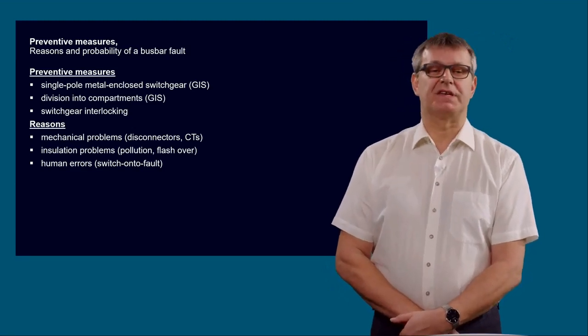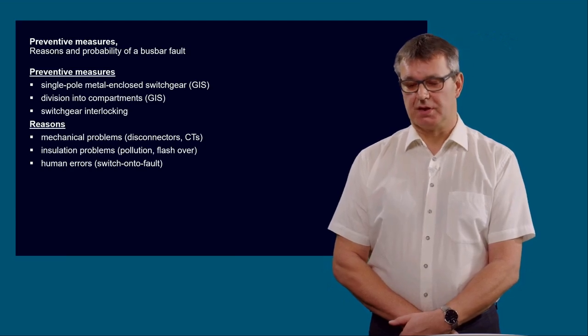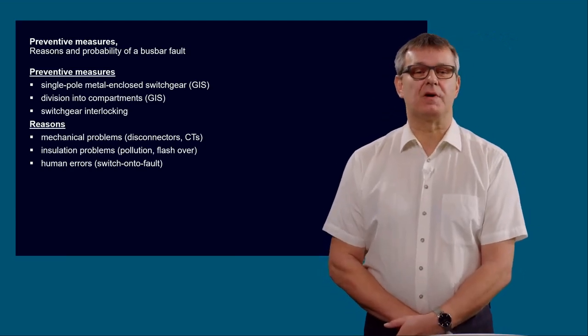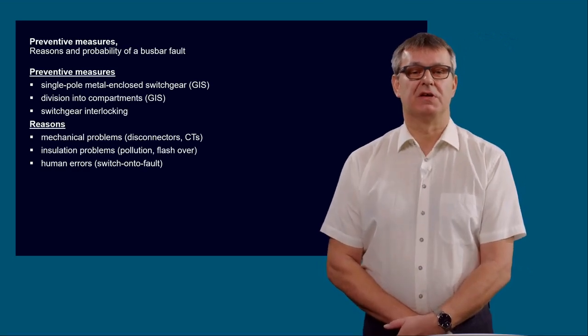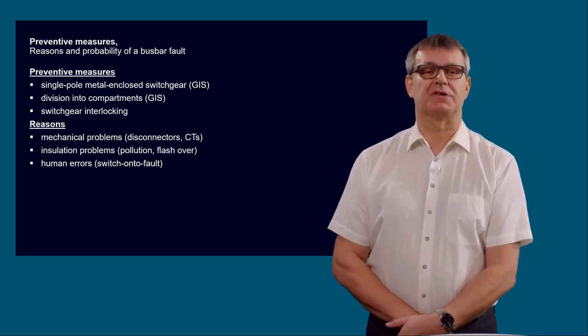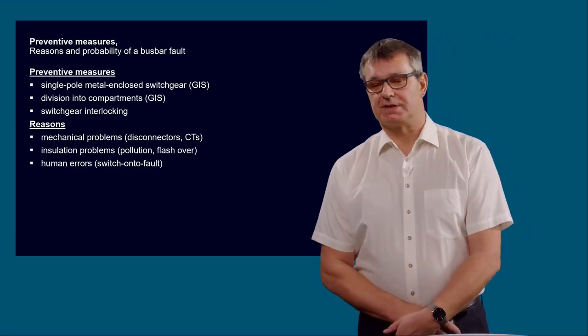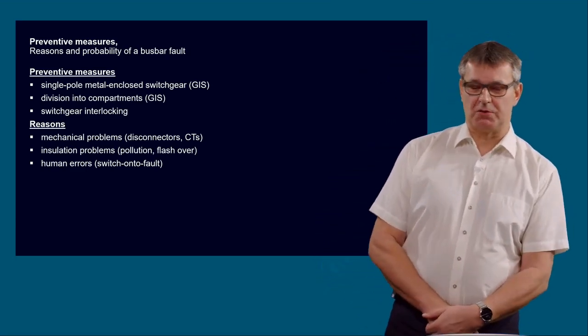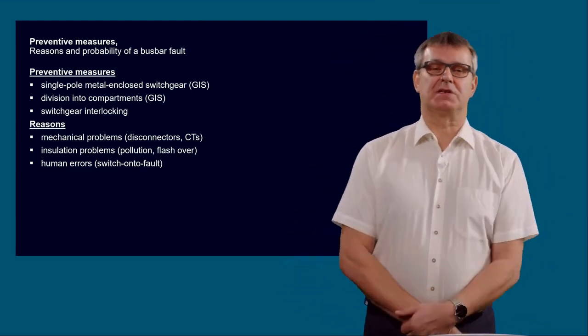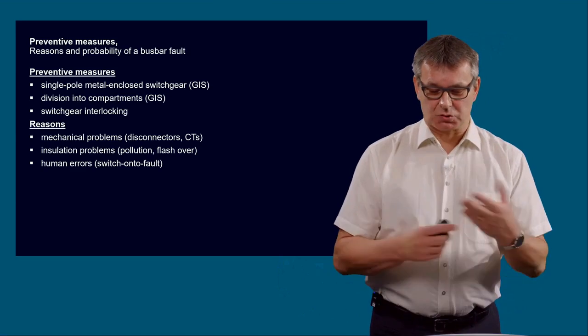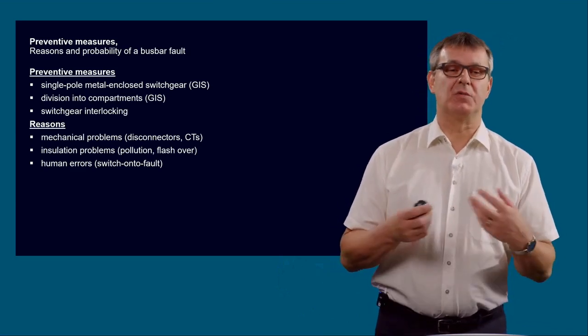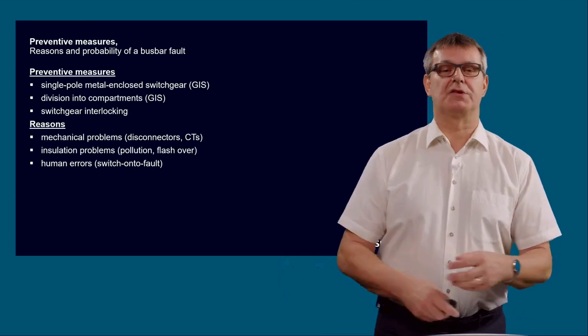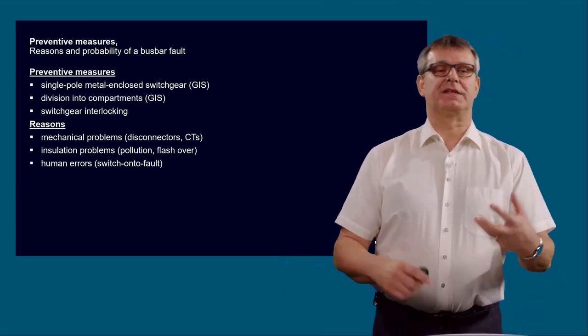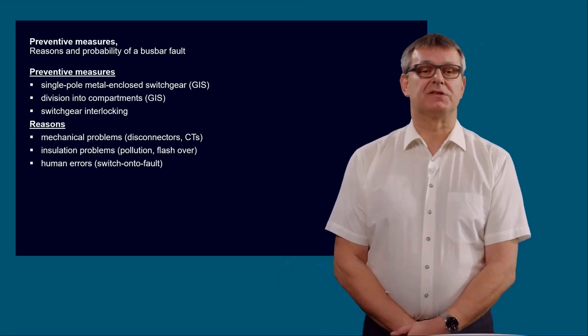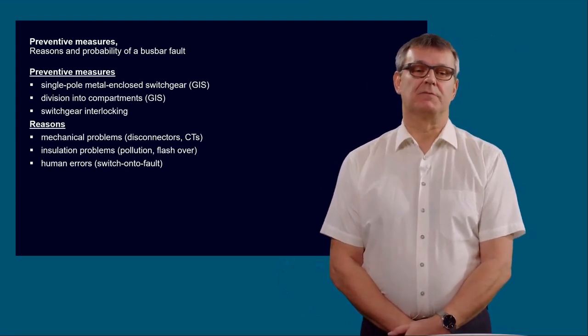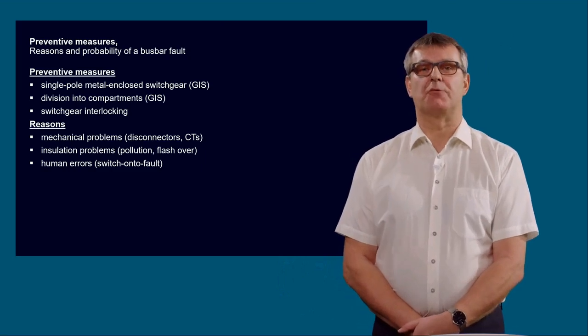And I would say the most likely reason for busbar faults is human error. So typically the switch-on-to-fault errors. For example, during a maintenance activity, the cable or the busbar has been earthed by some cable. The maintenance activity was finished, and somebody forgot to remove the earthing cable. And then we have a typical switch-on-to-fault situation, which is basically a human error.